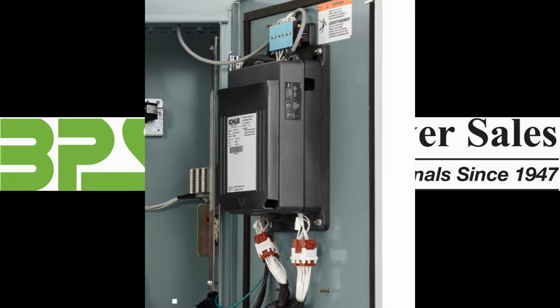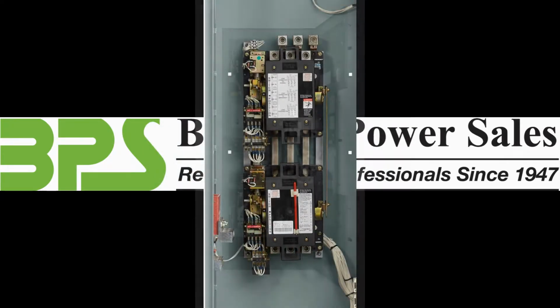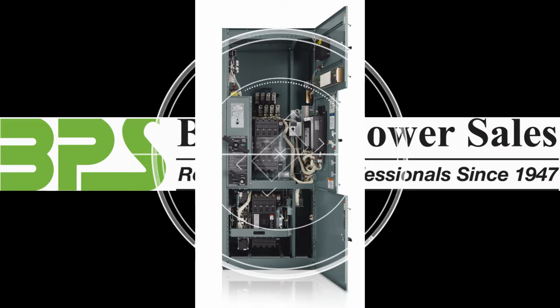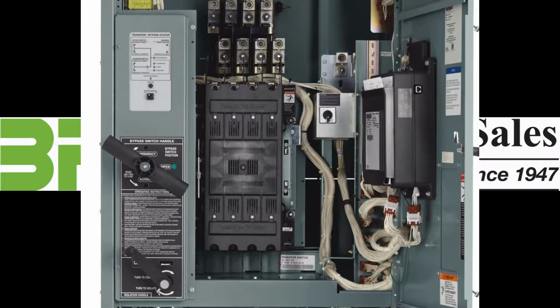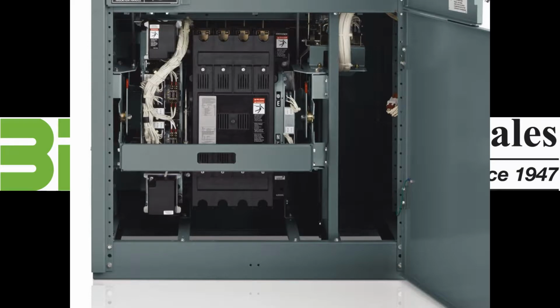There's basically two parts of the transfer switch. Typically on the door is the controller. I like to refer to that as the brains. And inside is the switching mechanism, the brawn. Here we see a bypass isolation switch with the doors open. So let's focus in on a bypass isolation transfer switch. Again, we see on the right the controls, but instead of the transfer switch, this is the bypass switch. We find the switch down below, and here we can service and maintain it, draw it out to a test position, and even take it out to be able to service and maintain it.